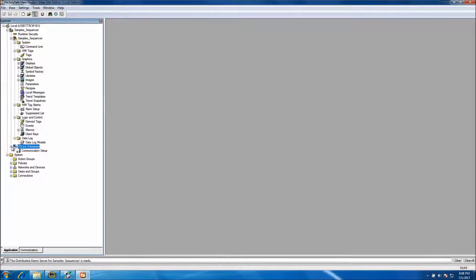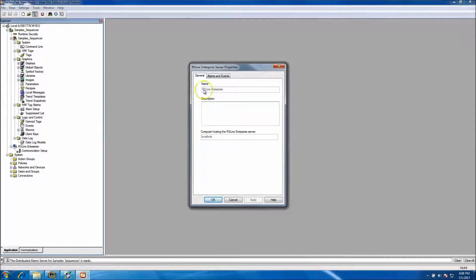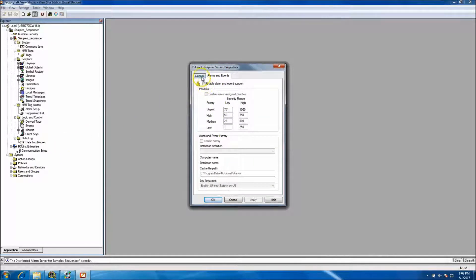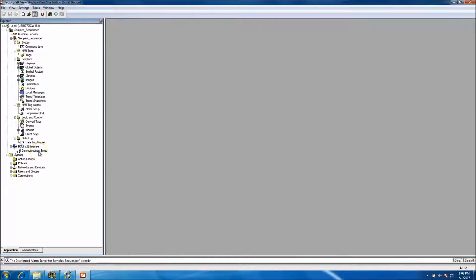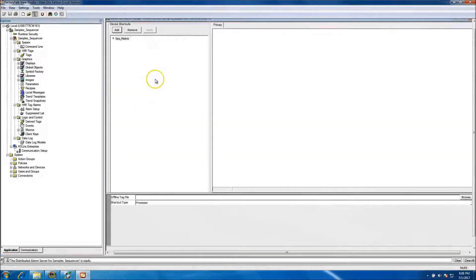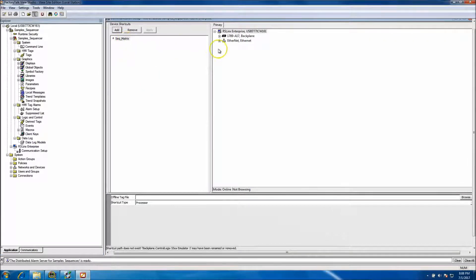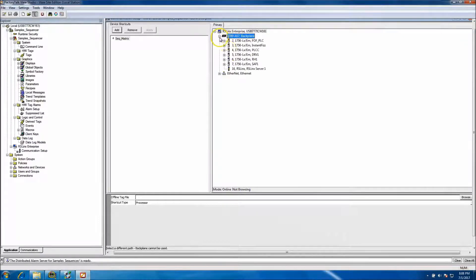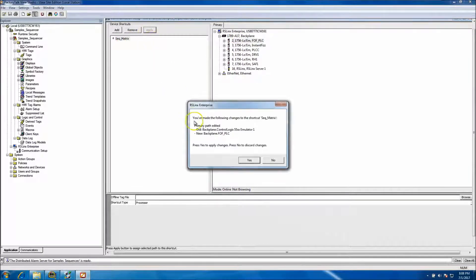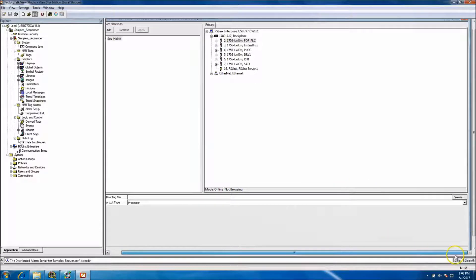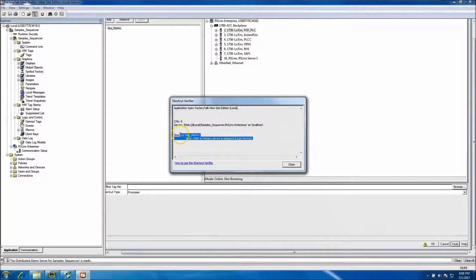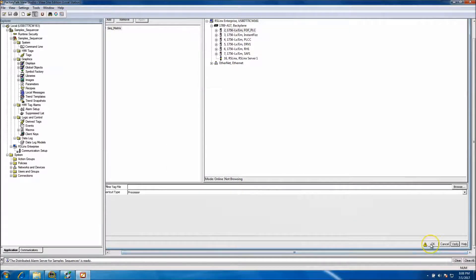There are a couple of key factors to look at. First, right-click your RSLinx Enterprise — for alarms and events, if you're not using any, just verify that. Go to communication setup and you'll see your shortcut is already in there. You need to set up your shortcut for whatever path you're on. In our case we're using the 1789, which is the virtual backplane, and we're in slot 2. Click apply with it highlighted, then at the bottom click verify to make sure the shortcut took.